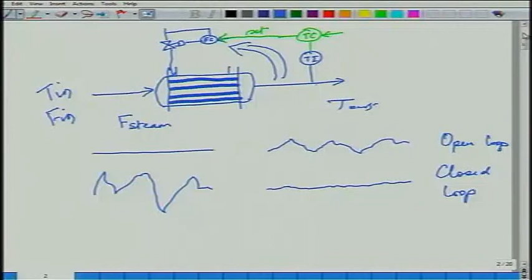And if you consider this perspective, you will find that, look, this actually makes sense. Energy management system, if something is going to go unstable, you want to do it the best possible way, use the closest possible handle. Product quality will always be an active constraint variable. Safety concern, you want to operate close to the flammability limit but not in the flammability region, right, tight control. How close can you operate will be determined by how tight you can control it. Same thing with environmental, zero discharge or minimum discharge, right? You want to control these things tightly. So put in place loops that help you do that. When you put in place the loops, variability in these variables gets transformed to whatever you are manipulating.